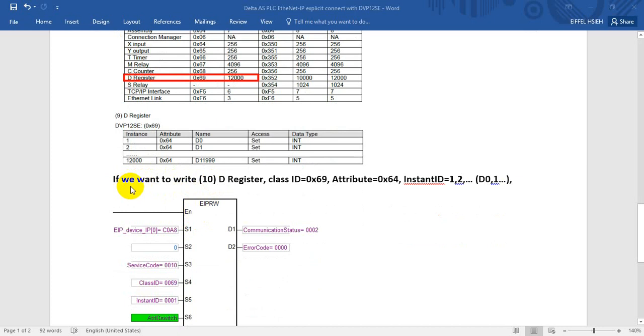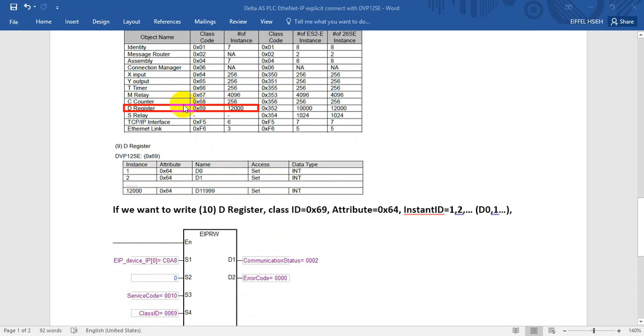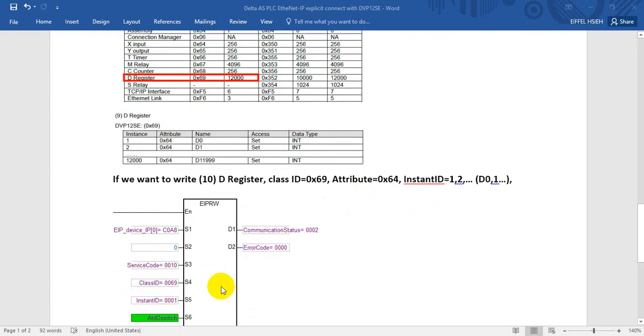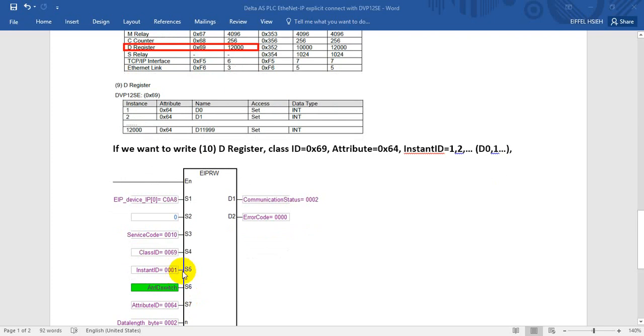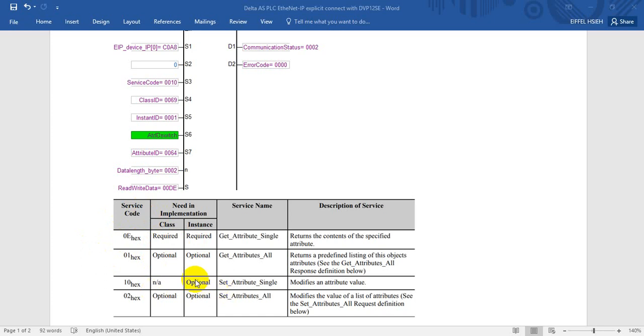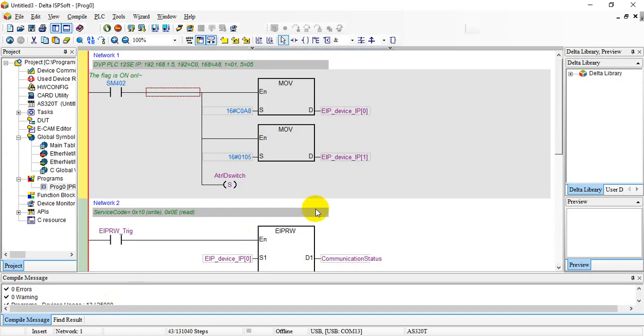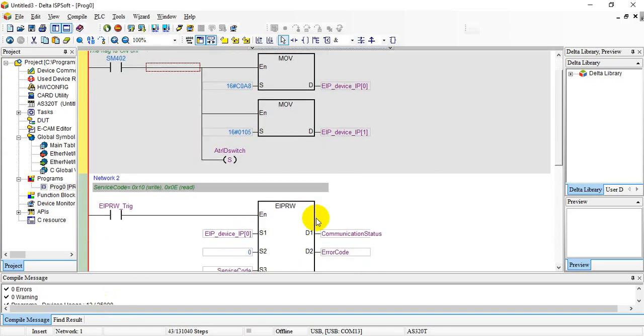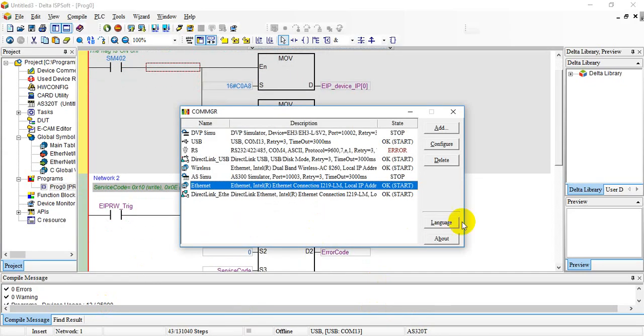Later we will show the example of the data register. You can see it's under class 69 and attribute 64. The instance ID here means if we want to read D0 then it will be 1, then D1 will be 2. In EtherNet/IP we also have function code like Modbus, and here we call it service code. As we just mentioned, if we want to write then we will use 0x10.